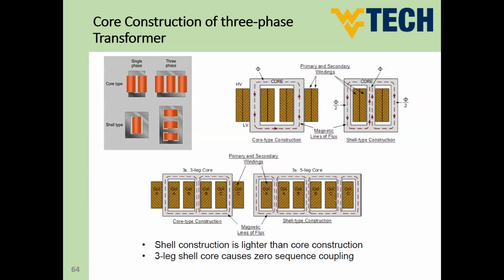Okay, so what is the difference? What happens if we have this kind of flux distribution inside our cores? Shell type construction is lighter than core construction. Shell construction is lighter than core construction. A three-leg shell core causes zero sequence coupling.